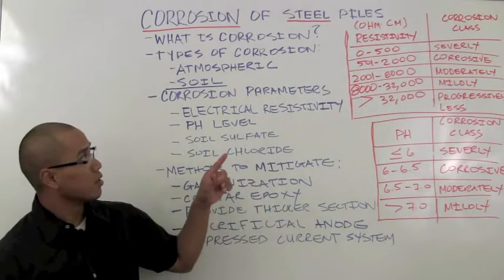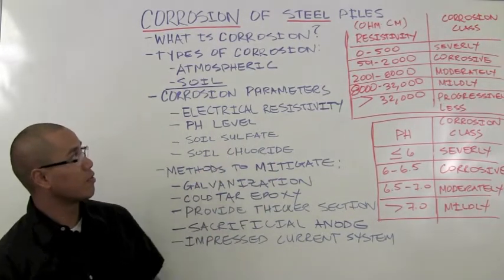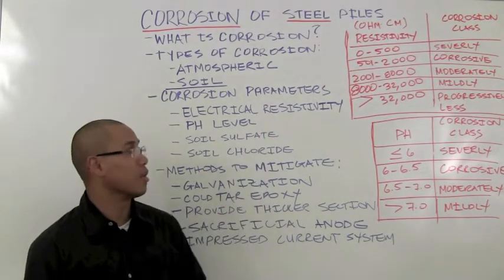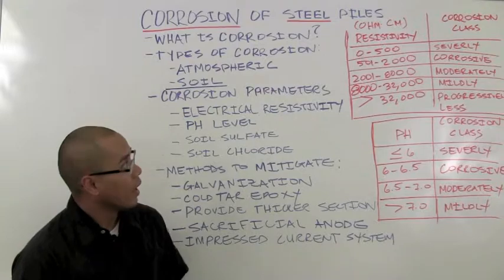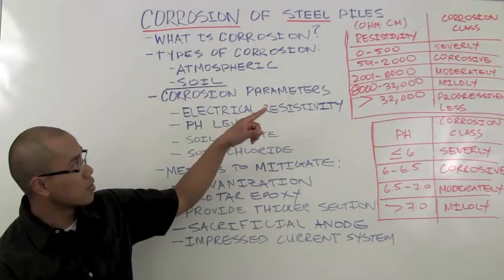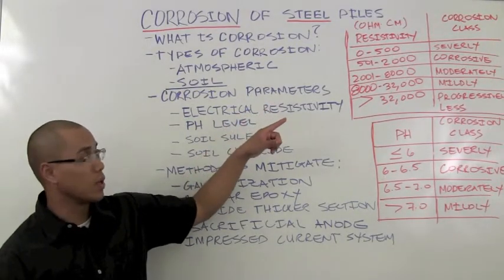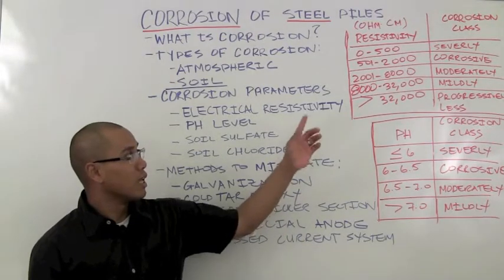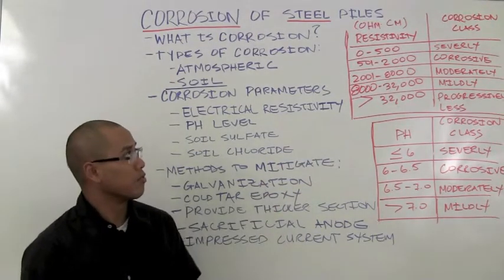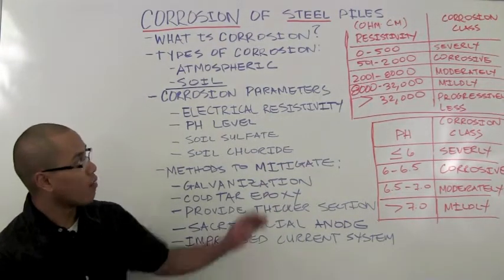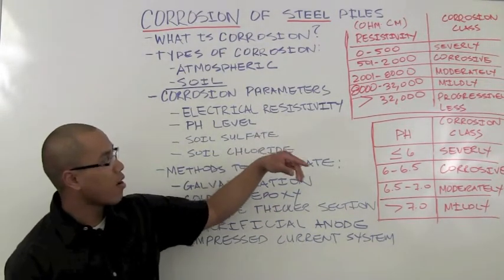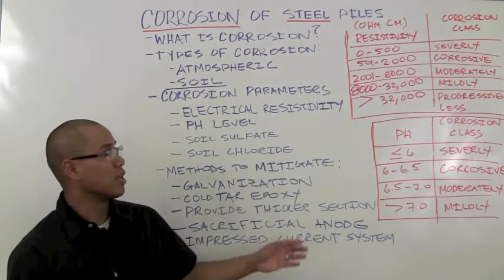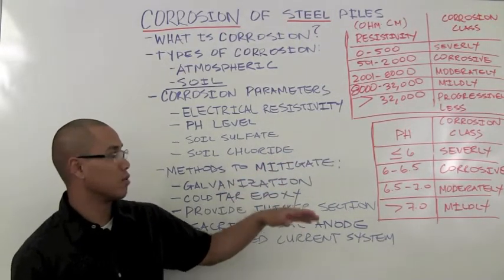As you can see in the table to my left here, resistivity is measured in ohm centimeters. At the top of the table, resistivity values between 0 and 500 would deem the soil to be severely corrosive. However, as you get higher in the resistivity values, the soil tends to be less corrosive.